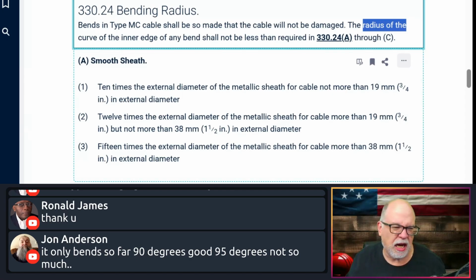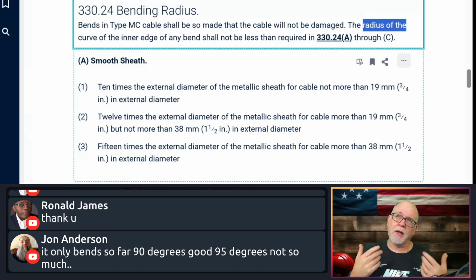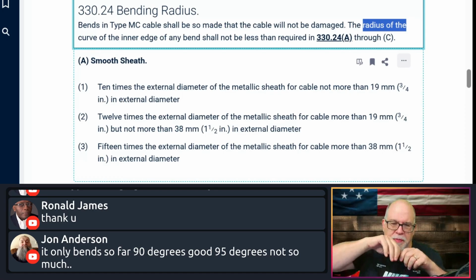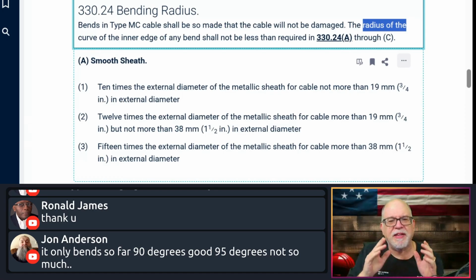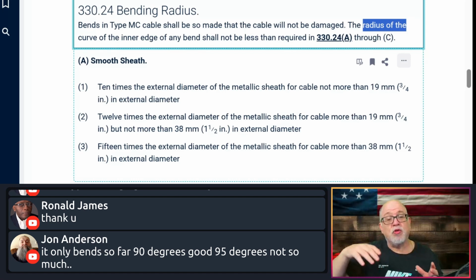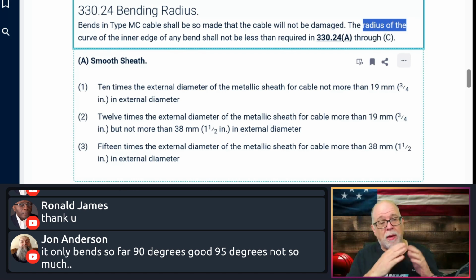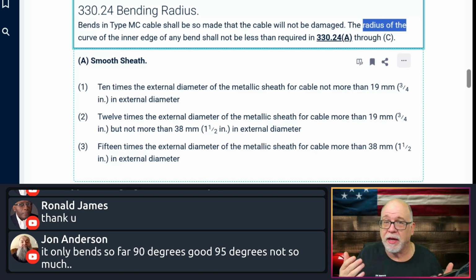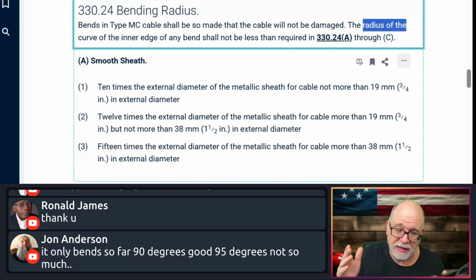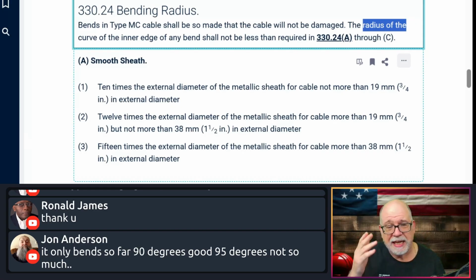But I'm going to be honest with you. When it comes to MC cable, when you're bending it, you're just going to bend it, but you're not going to bend it to the point where you blow out the back end. Where does this become a big issue? Obviously, larger MC. It's not as easy to mess with, and if you try to bend it a lot, you could blow out the back end and damage it. That's a bigger, costly expense because you're talking bigger conductors. Plus, it won't bend nearly as easy. But again, for bending, we don't care as long as you don't blow out the armor. That's the biggest thing, right?